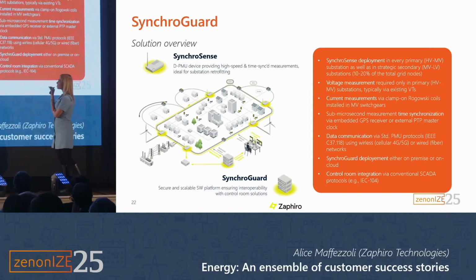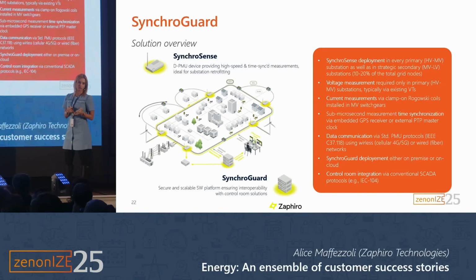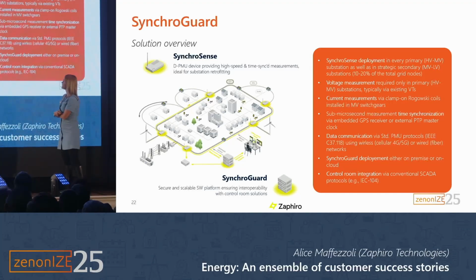Something more precise about what we offer at Zaphiro. We offer a solution called SynchroGuard, a platform that enables observability of the grid in real time with measurements, as I said, taken every 20 milliseconds, outage management, corrective maintenance, so information about faults and fault location, and also preventive and predictive maintenance based on incipient faults and on the capability of PMU to check everything that is happening in real time in the grid. And as I said, power quality events in general. We offer an integrated solution, hardware and software. Something that I want to highlight: we are a software provider, a solution provider. We also have the hardware that is an enabler for this solution to work.